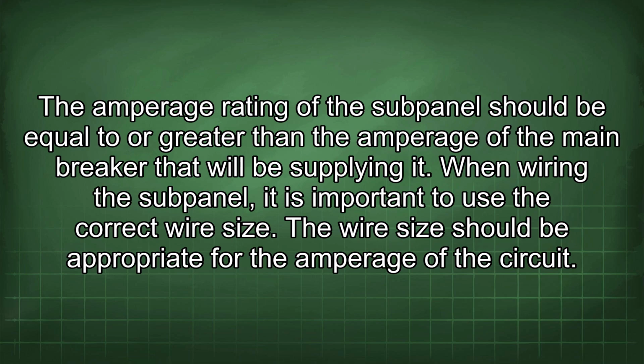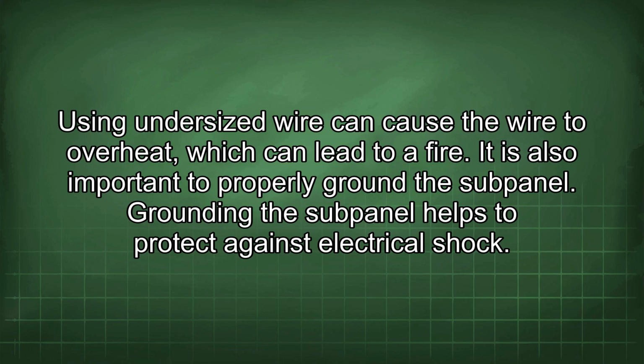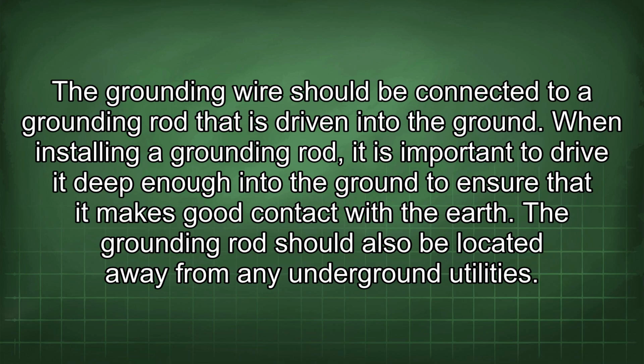The wire size should be appropriate for the amperage of the circuit. Using undersized wire can cause the wire to overheat, which can lead to a fire. It is also important to properly ground the subpanel. Grounding the subpanel helps to protect against electrical shock. The grounding wire should be connected to a grounding rod that is driven into the ground.